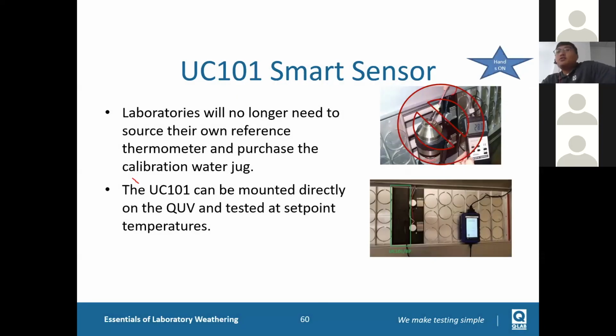Also, we will soon introduce our UC101 smart sensor. What is the UC101 smart sensor? Remember, in the QUV, I think everyone knows that the QUV needs irradiance calibration, right? Four spots to do the calibration check. We require you to do the check every 500 hours. But how many of you know that the QUV needs temperature calibration, just like the QSUN? In our operation manual, it is required every 6 months. But I know that the reality in the field is that many customers ignore that. I know that. So I'll give you some information about our improved temperature calibration of the QUV.